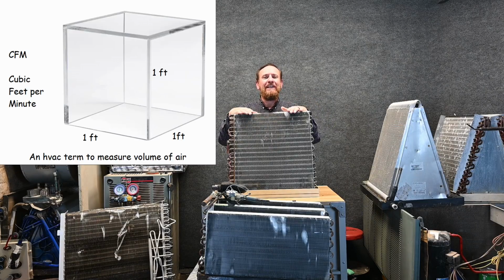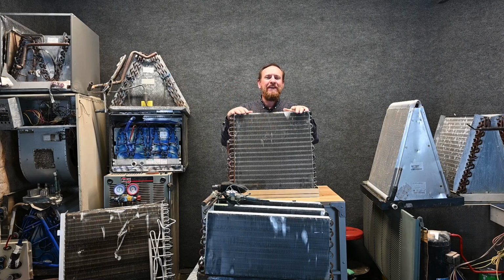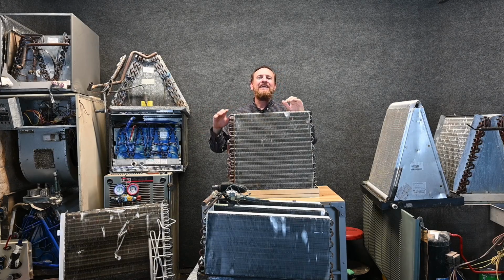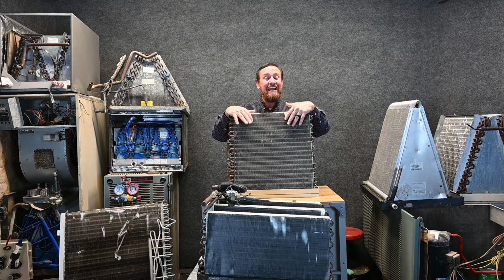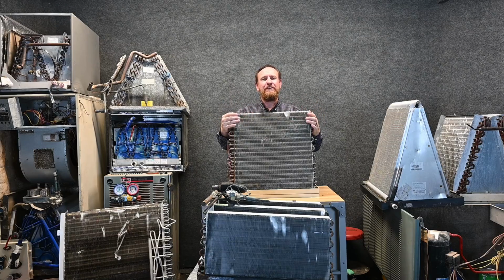It's going to depend on the climate. If it's a humid climate, we typically want less CFM of air going through here. And if it's a very dry climate, you typically want more CFM of air. How do you know how much CFM of air? The manufacturer's instructions is a great place to start. And when we get further into ductwork and AC and psychrometrics, we'll go into that in more detail. But right now, just understand that airflow does make a difference in how well this thing performs.